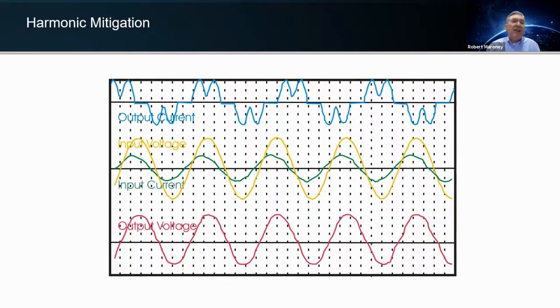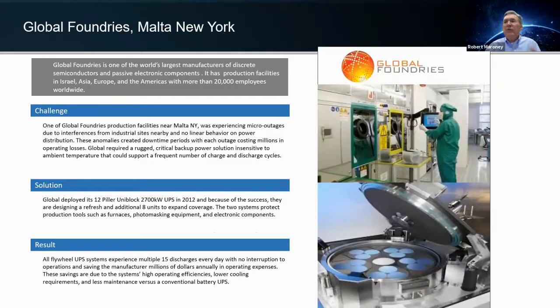And what's nice about that on the input, you'll see that there's no propagation of harmonics to the input voltage waveform that can have an impact on your infrastructure, whether it's your lighting in the building or sensitive equipment, or for that matter, your power generation that might not be able to get on the bus with high harmonic currents in today's economy. So let's take a look at where we apply some of these things.